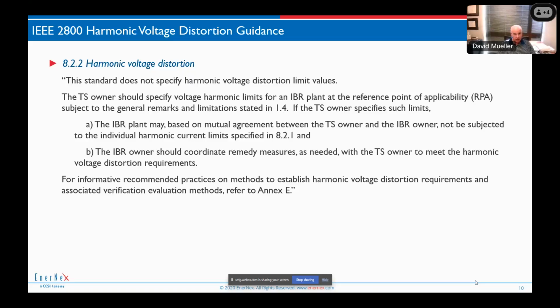What I want to suggest is that if a transmission system operator in the US does establish harmonic voltage limits, I will be very surprised if they do anything but go to IEEE 519 2022 and take those harmonic voltage limits straight from that standard, because that's what they're held to. That's what they're held to. So I'd be surprised if they would go anything different. There are problems with those limits, as I mentioned earlier. The fact that some places don't meet those limits currently. So this is an interesting clause.